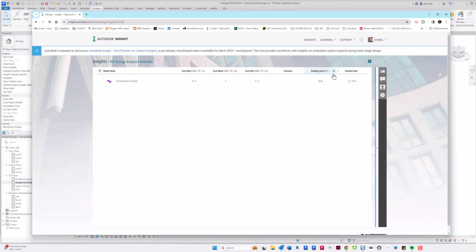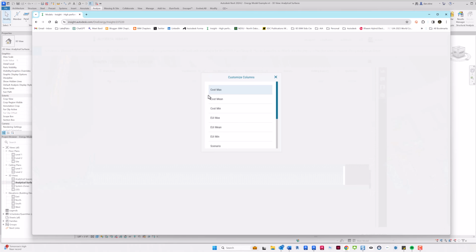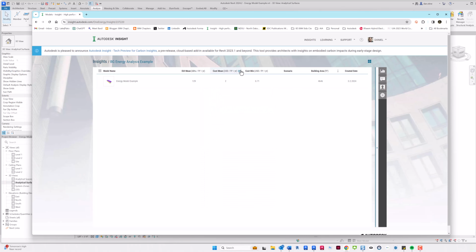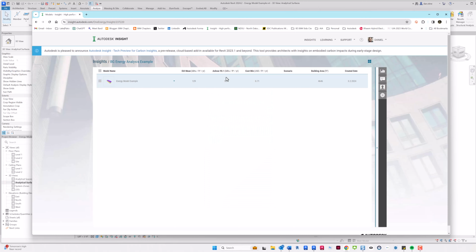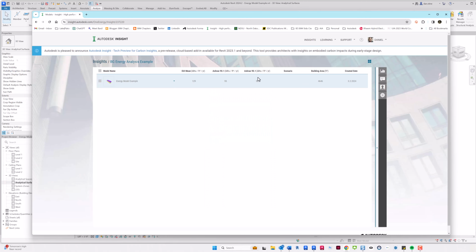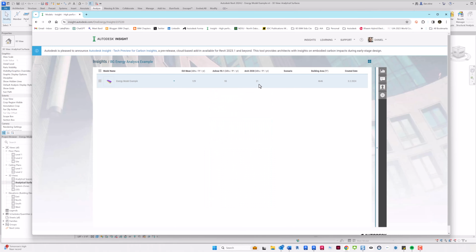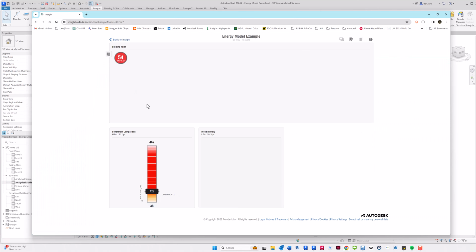And then if we switch this to a row and show the EUI mean, ASHRAE 90.1 2010 is what this is hardwired to. It has a connection to the Architecture 2030 zero tool, so that would be the zero tool number. And the square footage just as a double check. And so 129 obviously is high, but that's the mean.